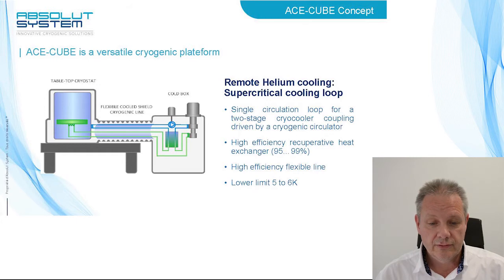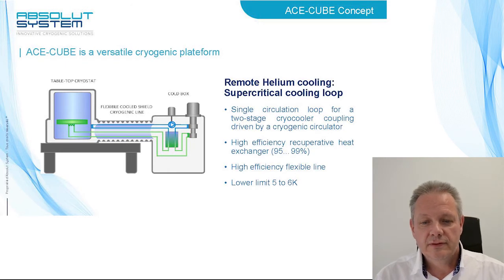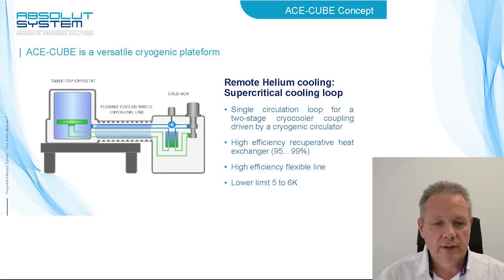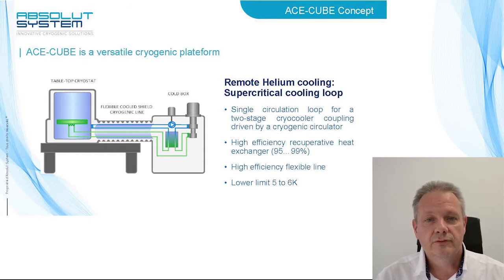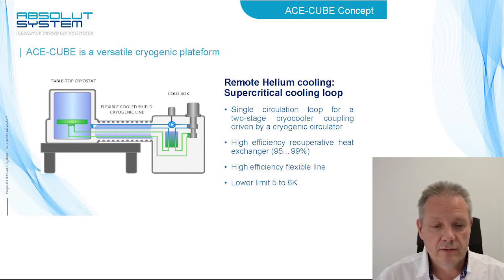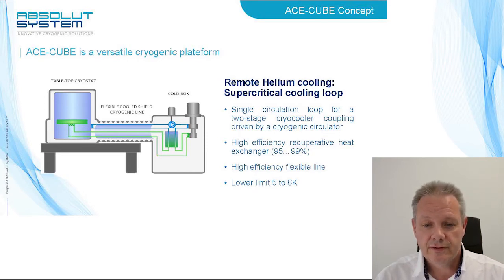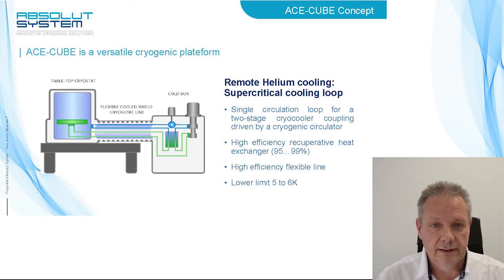Vibration-free closed-loop cryostat for low-temperature physics in the 1 to 40 K region. The ACE-CUBE concept comes with the development of numerous remote helium cooling loops or supercritical helium cooling loops. Few bars of helium gas are circulated by a cryofan from the cold box, where the gas is cooled by a cryocooler, to the application cryostat via a high-efficiency vacuum-insulated flexible line.